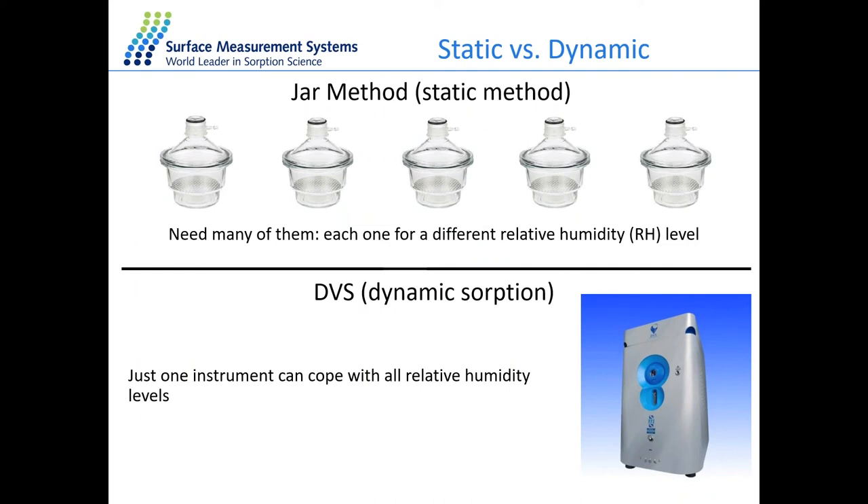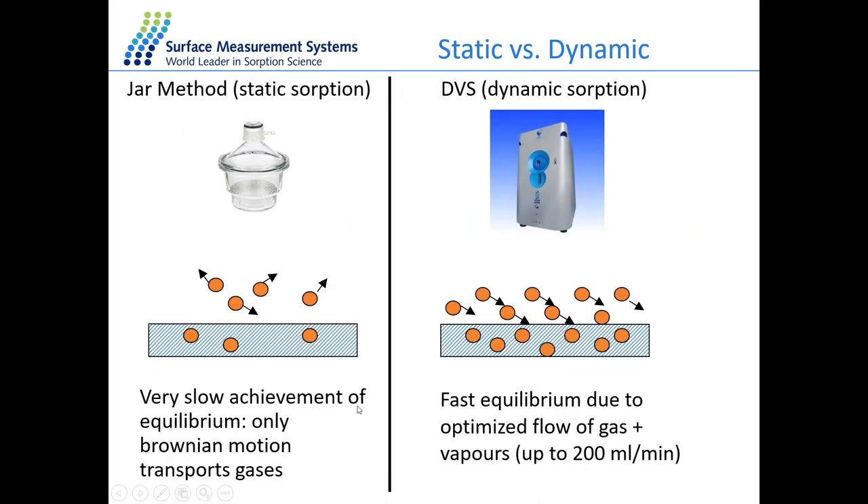We can compare DVS to a static method — the jar method. In the static sorption method, equilibrium is achieved very slowly because it only depends on Brownian motion of molecules being transported. In DVS, we have fast equilibrium with optimized flow rates, giving us more control over the species interacting with our material. Whereas the jar method can take a couple of weeks or even a month for a single data point, with the dynamic vapor sorption method, we can complete a whole experiment in less than a day.